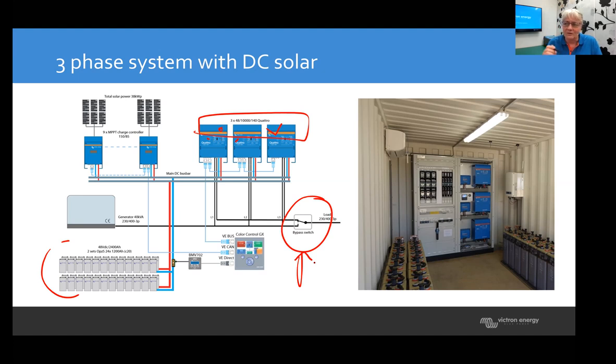Your generator connects straight to your loads, bypassing the Victron part — or if maintenance is needed, a replacement, or you need to work on the system while the rest still needs power. That's another good reason to put a bypass system in, so you can do maintenance and the site still has power from the generator temporarily.